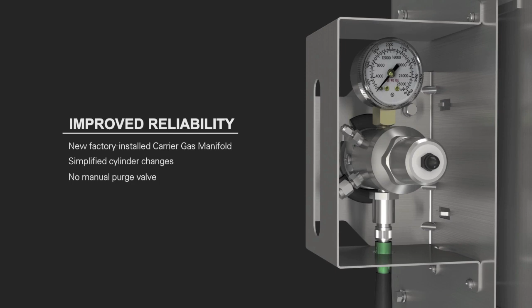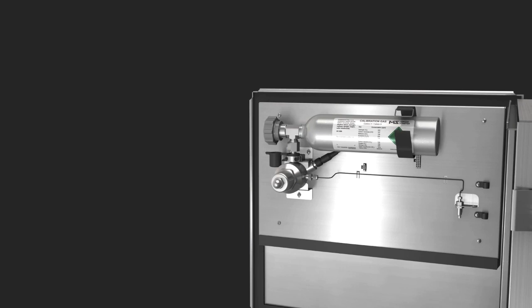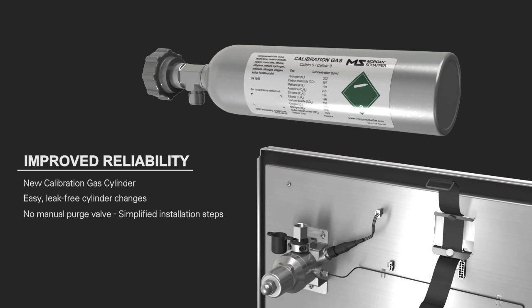Introducing the new Callisto 501 and Callisto 901 models. A new carrier gas manifold is now factory installed on the Callisto 5 and 9 units, simplifying both the installation process and cylinder changes. A new calibration gas cylinder has been developed to allow for easy, leak-free cylinder changes. The manual purge valve has also been removed for a simpler installation process. Routine maintenance has been reduced by increasing the lifetime of the calibration and carrier gas cylinders to 4 years. Data storage has been extended from 6 to 8 years.